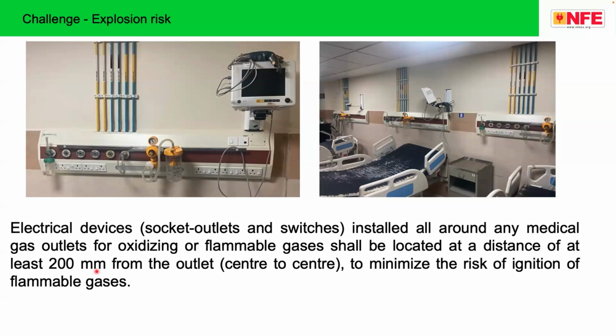But most often when we visit a hospital, what we see is this minimum 200 has been misunderstood as maximum 200. In most of the cases, the distance is much lower than 200 mm. Please make it very clear that the minimum distance between the electrical sockets and the outlets for gases is 200 millimeter. You make it 300 or 400, which is much safer.